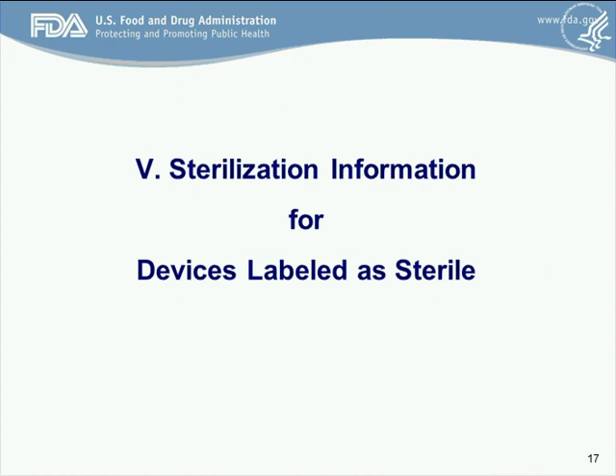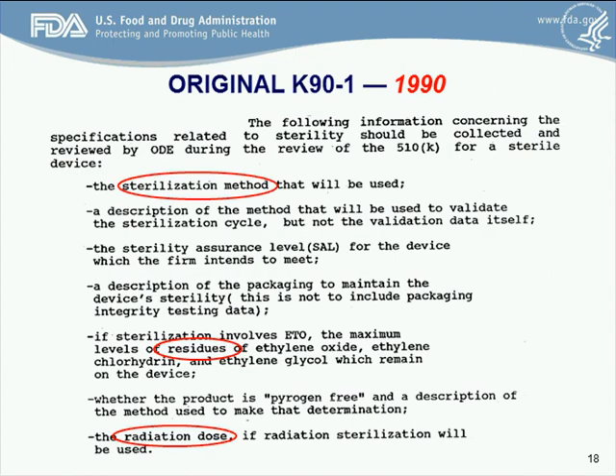That leads us to Roman numeral five of the guidance document — sterilization information for devices labeled as sterile. Going back to 1990, the very first guidance document, we were looking at a number of items: the sterilization method, the method used to validate the sterilization cycle, the sterility assurance level, the description of packaging designed to maintain the product's sterility, ethylene oxide residuals if applicable, whether the product is labeled pyrogen-free and the method used to make that determination, and the radiation dose if radiation is used.